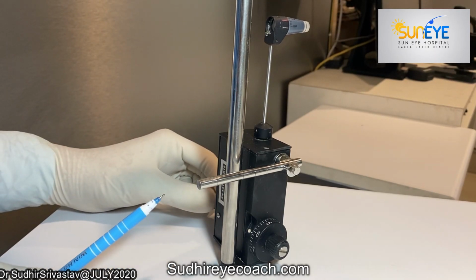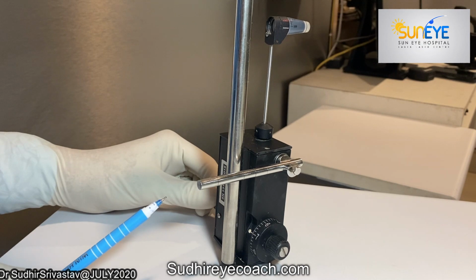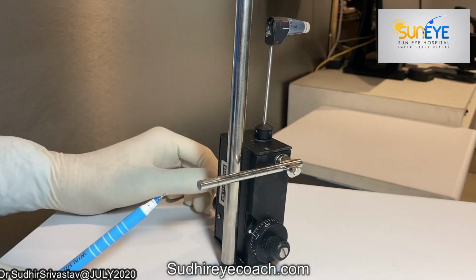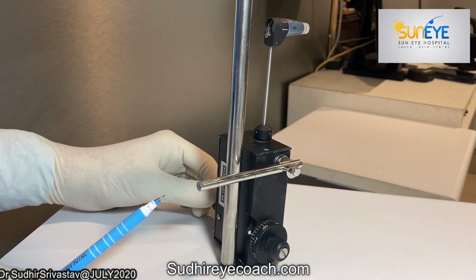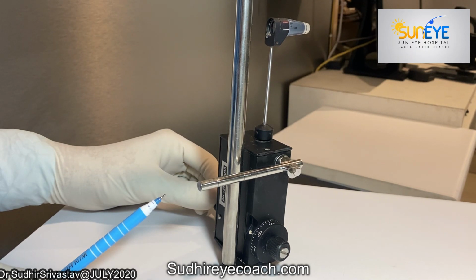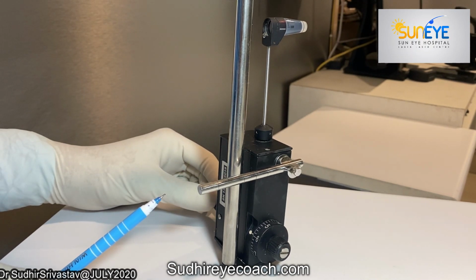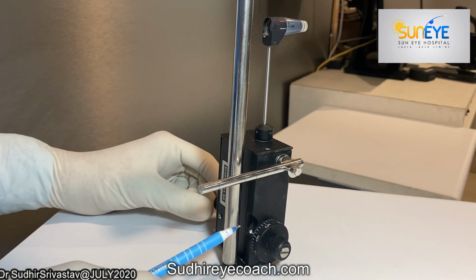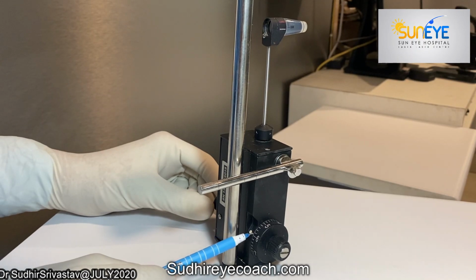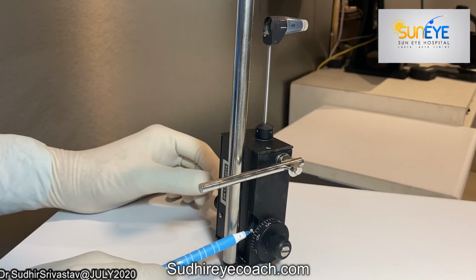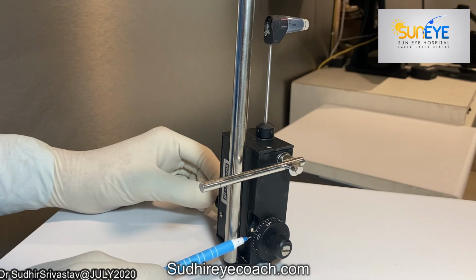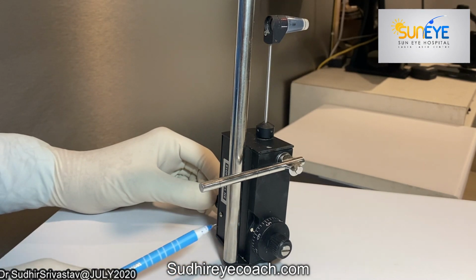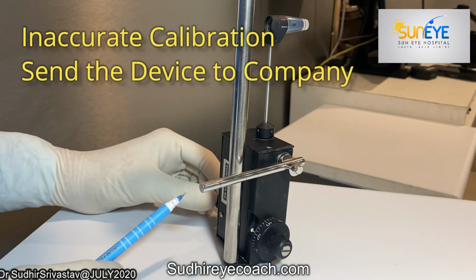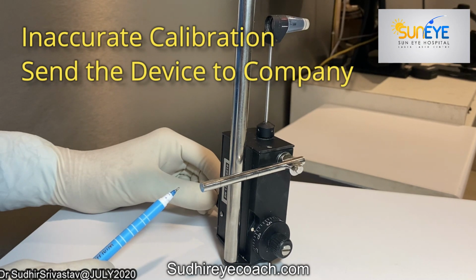Now again we move the knob towards the reading 7, and we go back towards the reading 6. Here we have seen the movement. Now if the reading falls again within 58 to 62, then the applanation tonometer is said to be in good calibration, otherwise not.